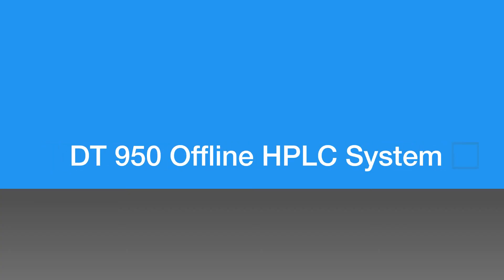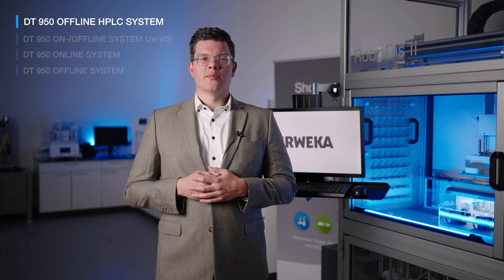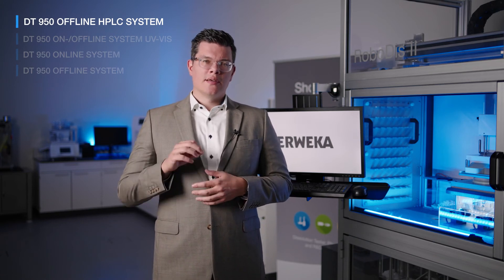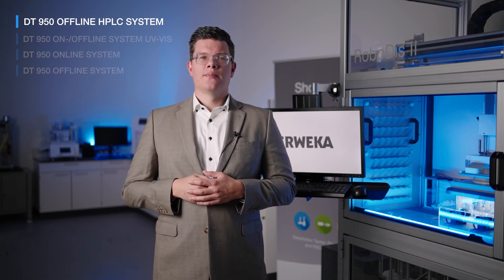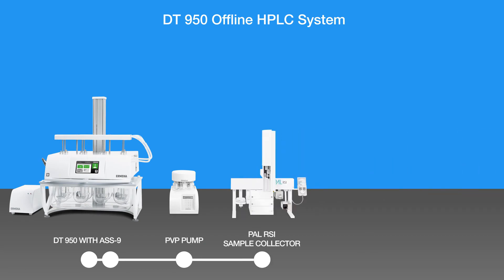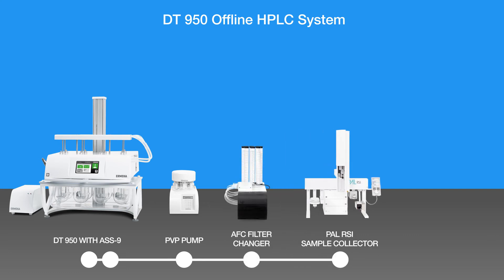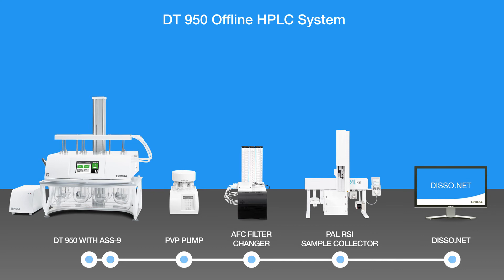The dissolution offline HPLC system is similar to our standard dissolution offline system. It is not connected to the analytic device and does automatic sample collection, but specifically for HPLC. The sample collection is done via a PAL-RSI autosampler, which offers a variety of options from different vials to cooled racks. For secondary filtration, the system can be configured with an automated filter changer. Our dissolution HPLC offline system is of course controlled by our disso.net.